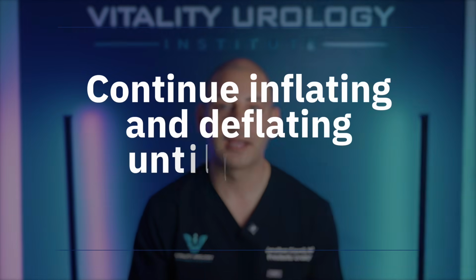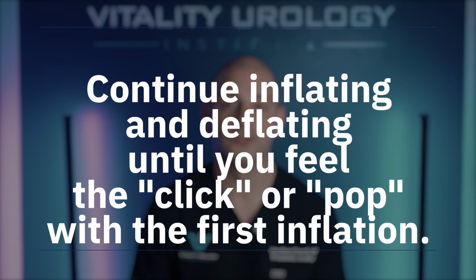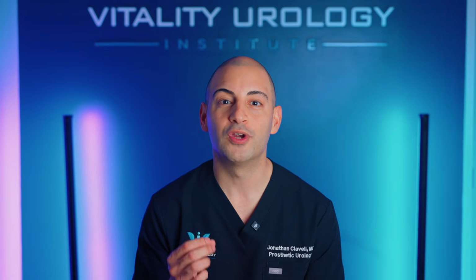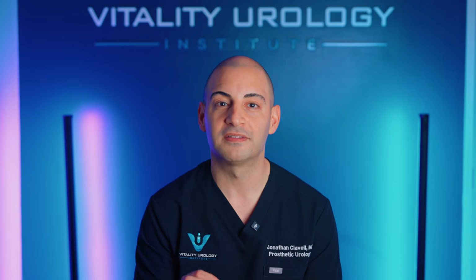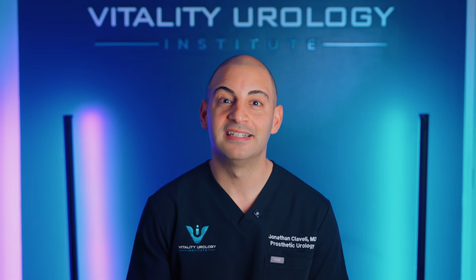Then try to inflate again. Sometimes that going back and forth between inflation and deflation solves the problem. How will you know that this problem is solved? Most of the time, you can feel that initial click or a pop when you start your inflation with the AMS pump. And that should let you know that the pump is not stuck anymore. Now, to avoid Stiction syndrome or the sticky pump, we recommend patients to cycle the device regularly, that is, every day or every other day.